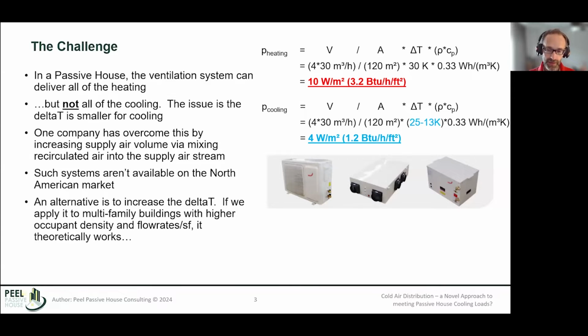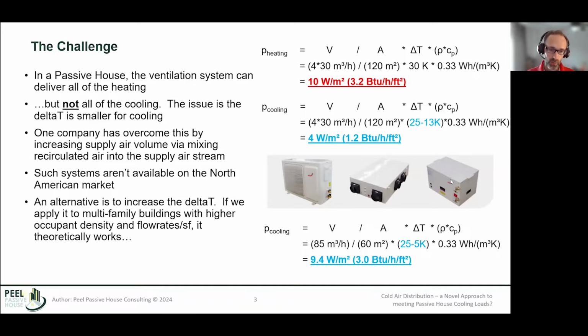But if we increase that delta T for cooling, plus we're dealing with multifamily buildings where the amount of air that we're delivering, let's say per square foot, is actually higher, there's higher occupant density, so we generally need more air per square foot. Those 2 elements combined can increase our cooling capacity, potentially closer to our heating capacity. And depending on the climate, this may actually be sufficient for meeting our cooling loads in a passive house.